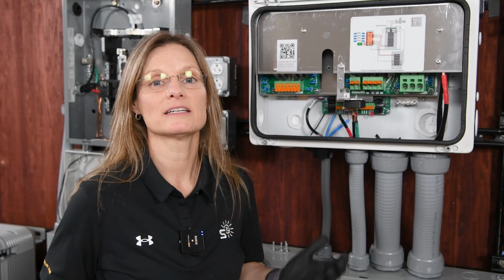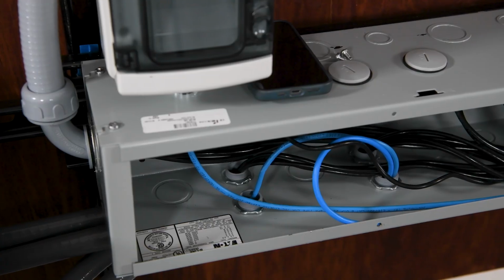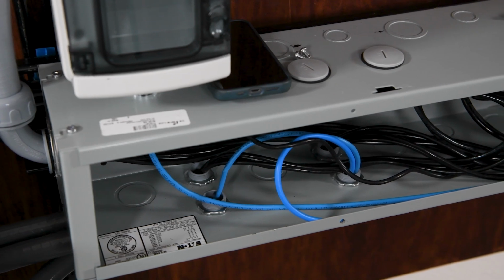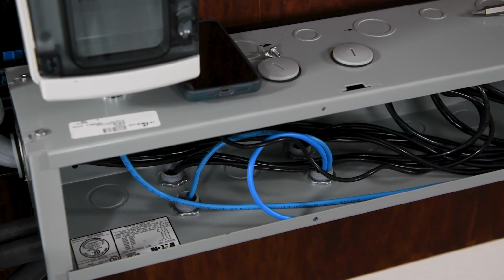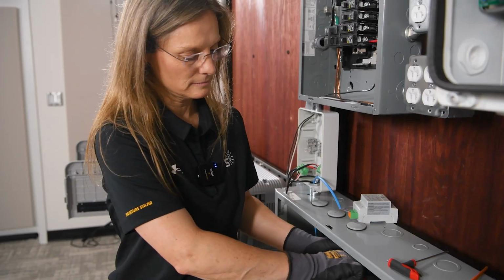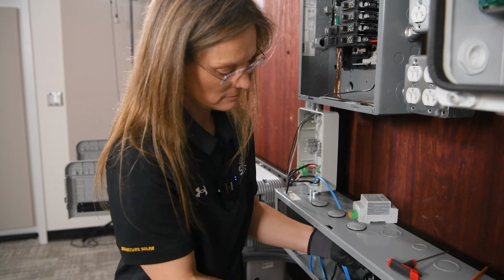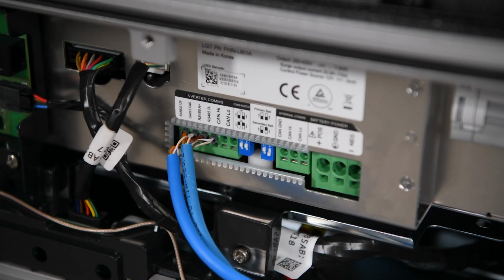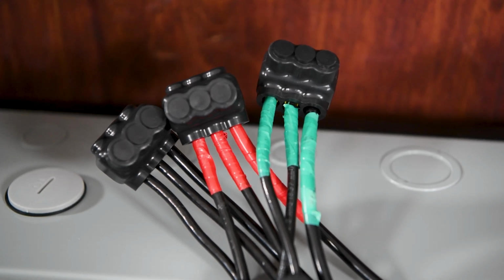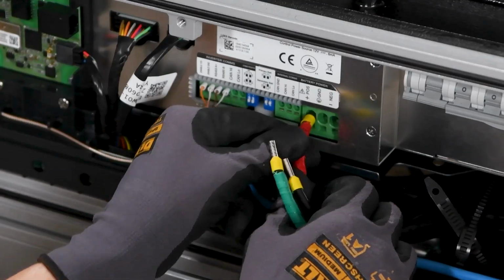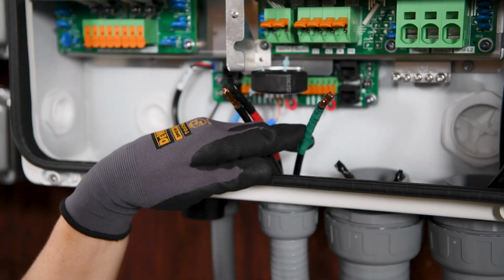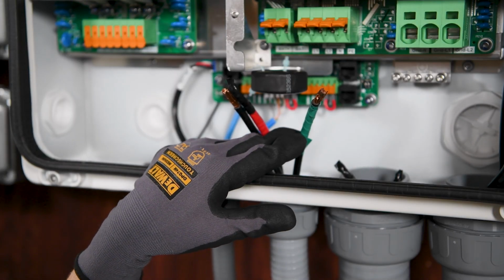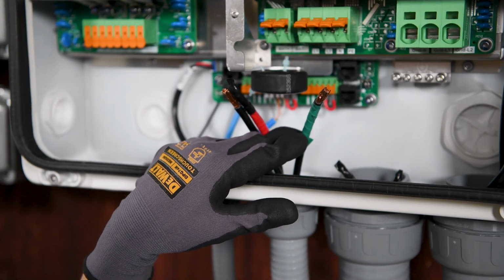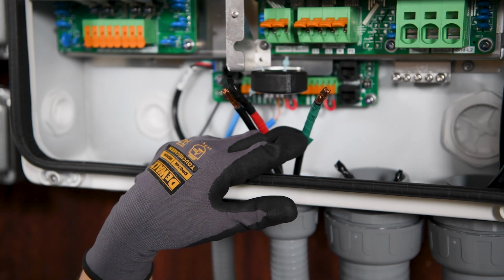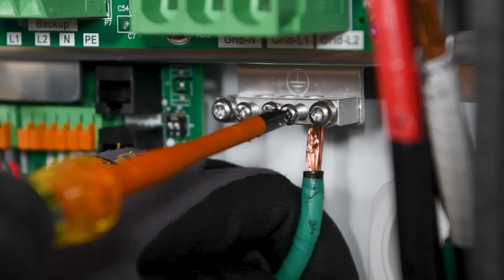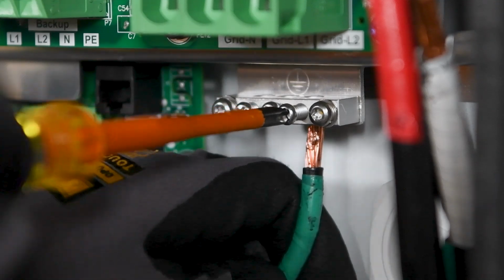Now, before we connect our wires to our inverter, keep in mind that we have already run all of our wires. We are just connecting our conductors from our wire trough to our inverter. We'll talk about all of that here in just a moment. Our batteries are not connected, but we do change wire sizes from our combiner box, from our batteries to our inverter. Here we have number 6 gauge wire coming from our wire trough to our inverter, and number 6 gauge wire is the max size that these inputs in the inverter can handle. We'll start with our ground wire going to our ground bus bar.